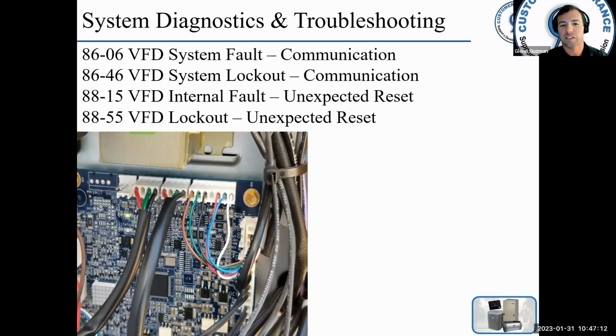8606 VFD system fault communication. 8646 is the communication lockout. 8815 unexpected reset, and 8855 the unexpected reset lockout. You see these codes go hand in hand, and these codes a lot of times go together with other codes. So going back to what I said before about looking at all of the fault codes together as a whole, there are some faults that occur that the PCM initiates a VFD reset.